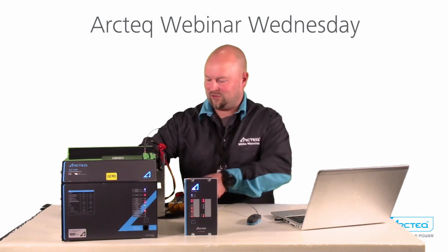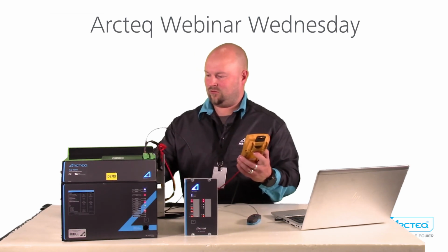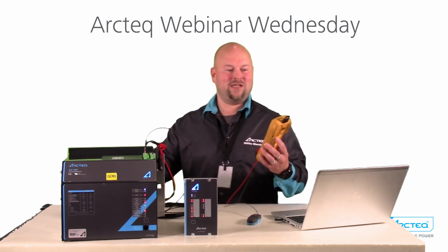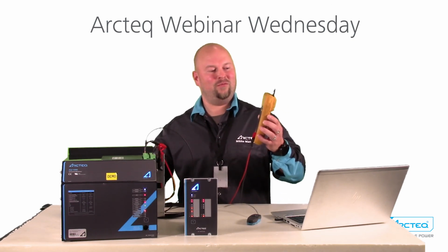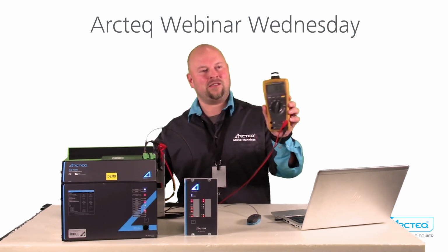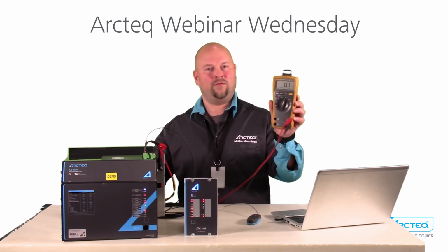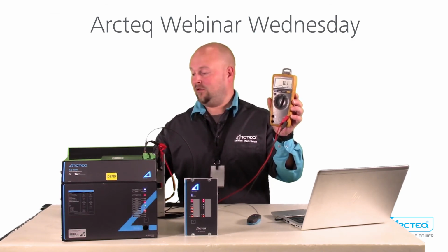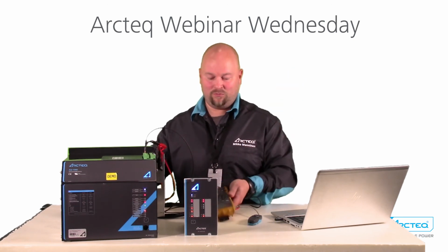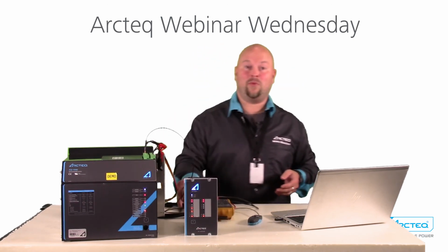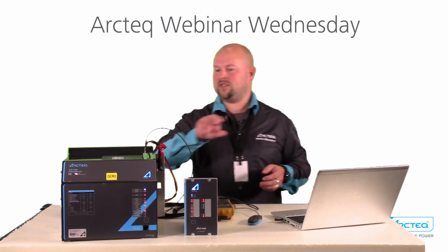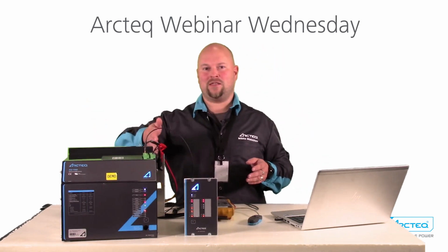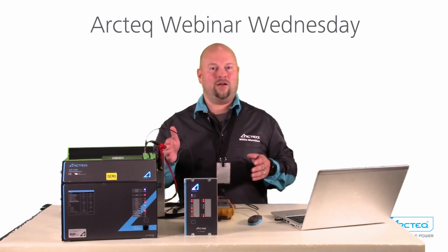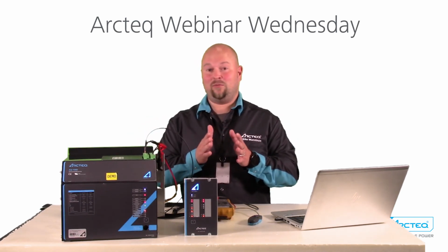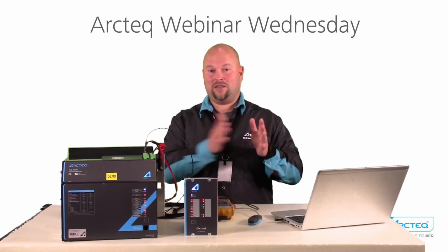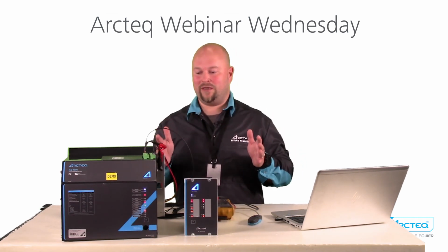Yeah, so many things to say that I may forget something, but this now shows 0.1 ohms, which is the most accurate reading you can get with this type of multimeter. But practically we are talking about micro ohms. It's a very pure single shaft movement, 3-phase closing simultaneously. So there are not practically any microseconds of difference. It's a very accurate 3-phase short circuit.